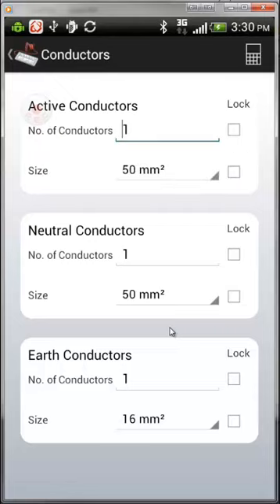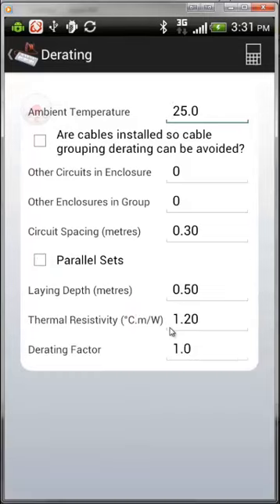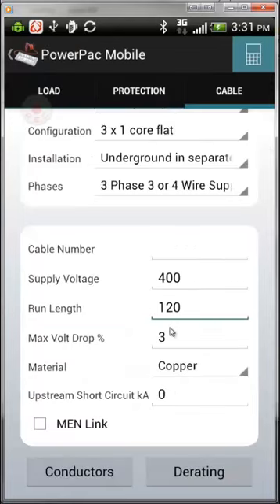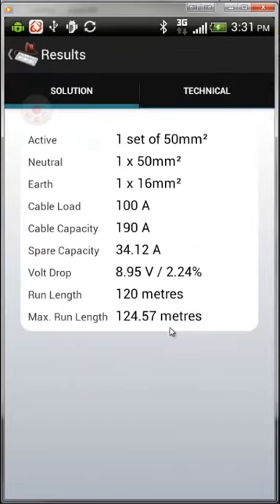You can also lock in cables here — if you have an existing cable installation and want to check the volt drop, earth fault loop, or the load that can be carried, lock that in place. You can also change the derating, put in parallel sets, override the ambient temperature, and adjust other settings.